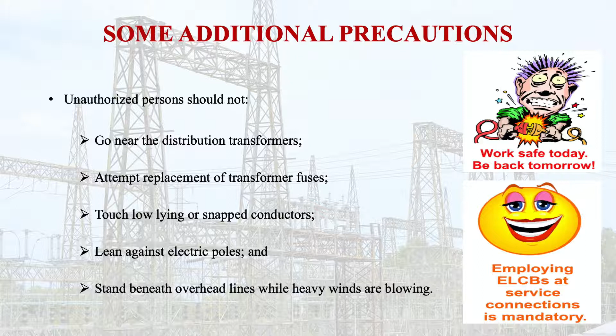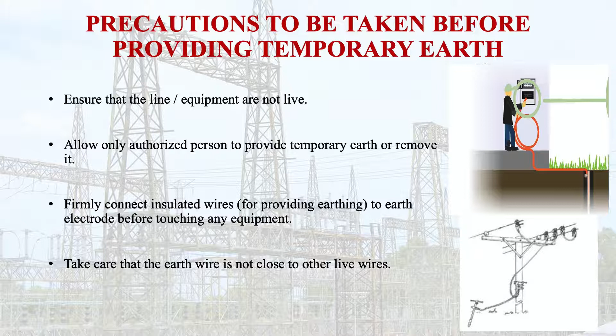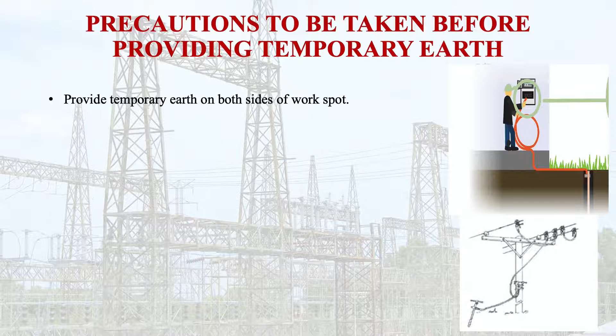So what are the precautions to be taken before providing temporary earth? These precautions are: ensure that the line equipment is not live. Allow only authorized persons to provide temporary earth or remove it. Then firmly connect insulated wire for earthing to the earth electrode before touching any equipment. Take care that the earth wire is not close to other live wires. Provide temporary earth on both sides of the work spot.